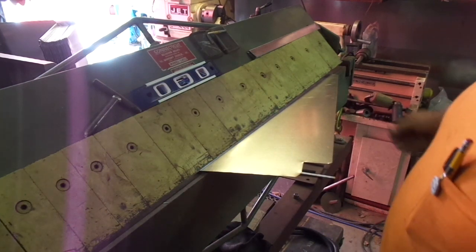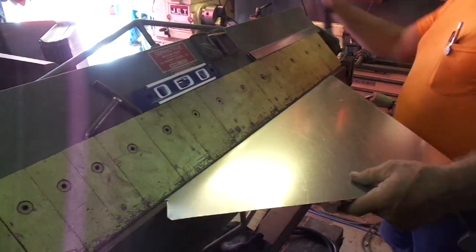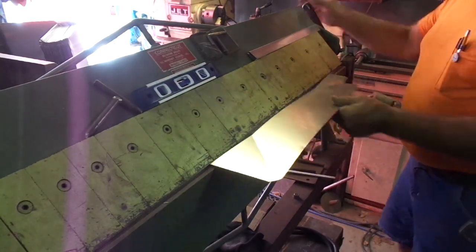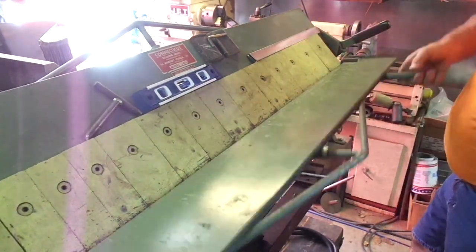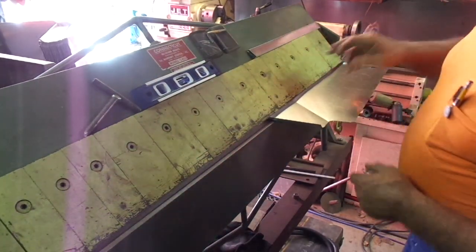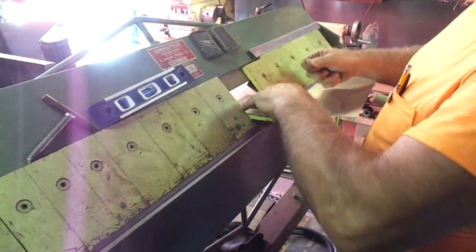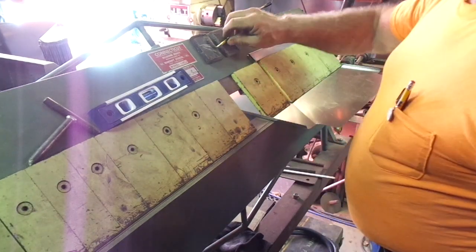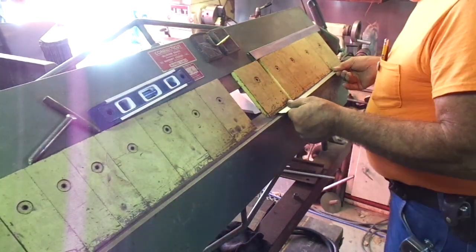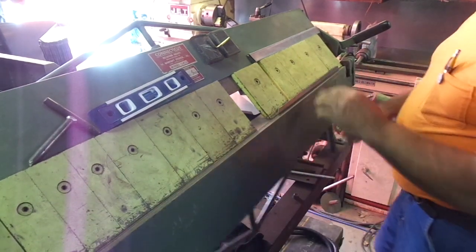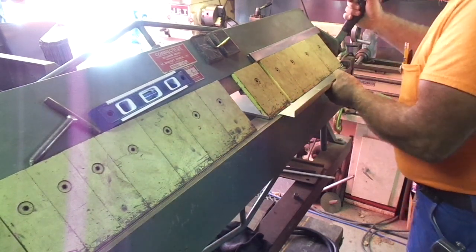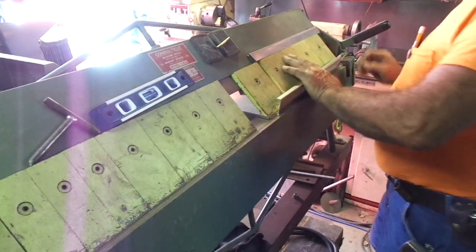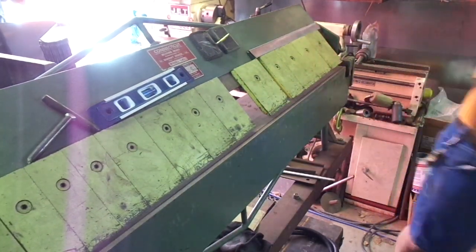If I remove that material, it should allow those inch and a half flanges to fold right in place here. It's not that critical. You can trim it as you assemble it, but it's easier to make it as close as possible to minimize all the aggravation once something is being assembled. There you go. We're ready to fold it. I'm going to go ahead and cross-break those, fold them, and then we're going to go ahead and see if we can assemble them. Now this is a box and pan brake. You don't really need the box and pan for this function, but simply because it's so convenient here, I'm just going to go ahead and use it. We've got our quarter inch bends.